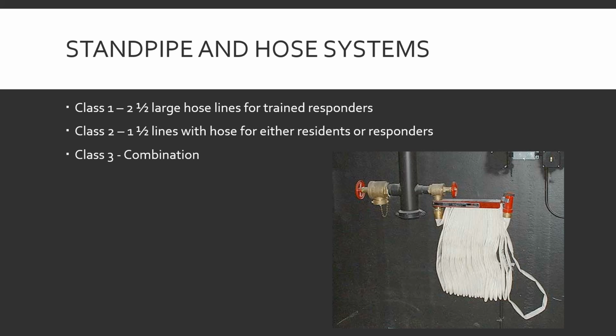Class 2, 1.5 lines with hose for either residents or responders. So this is, standpipe comes up and there's a smaller outlet and it's connected to a hose in the little cabinet or the wall rack, that kind of thing. Class 3 is a combination of both of the above. So our picture here, this is a combination, because it's got the big outlet here and the little outlet with the hose here. Now if it just had this and this same thing on this side, it'd be a class 1. And if it had 2 of these, it'd be a class 2. But a lot of them are a combination.